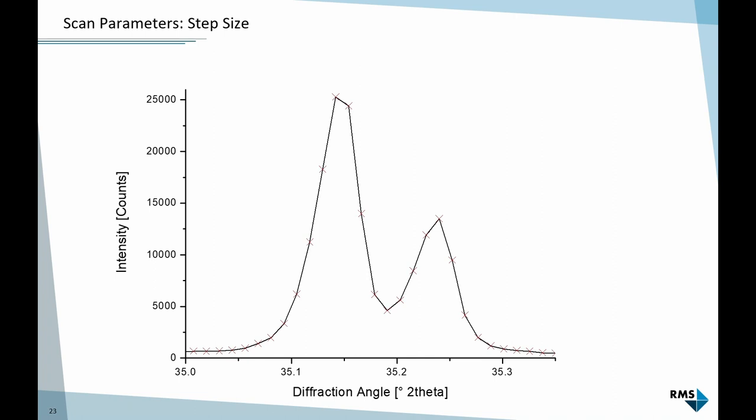The next parameter is step size - how often should we sample the pattern? There's a general recommendation that every peak should be described by at least five data points. In this example, if I consider this to be the main part of the peak, I'm using seven data points. The step size was 0.0122 degrees two-theta. This is what I want to achieve.